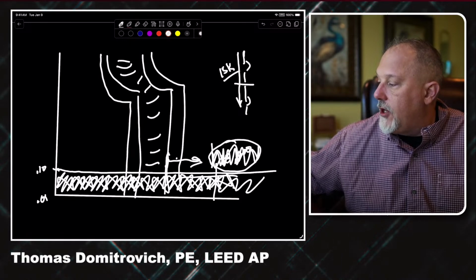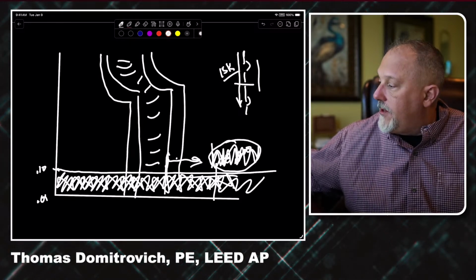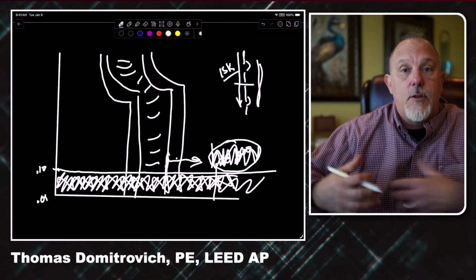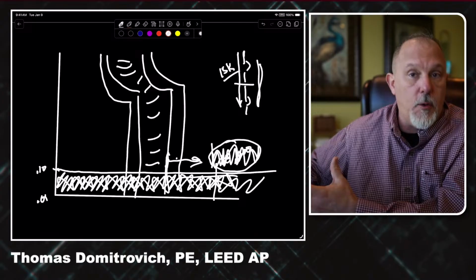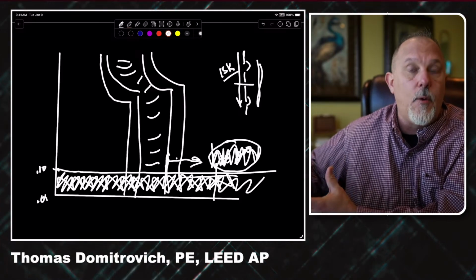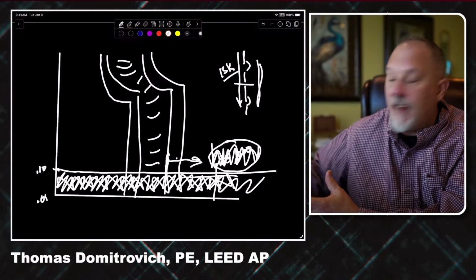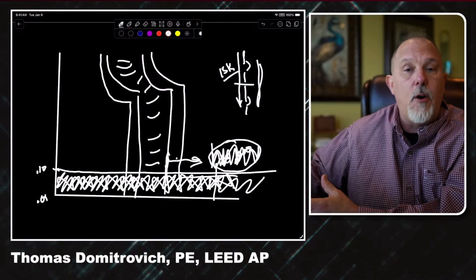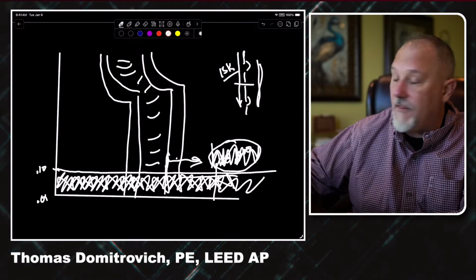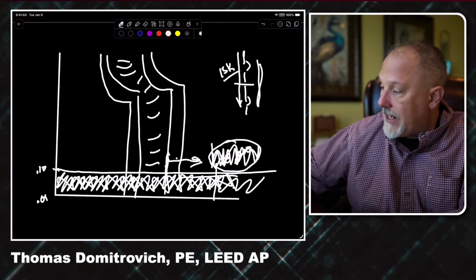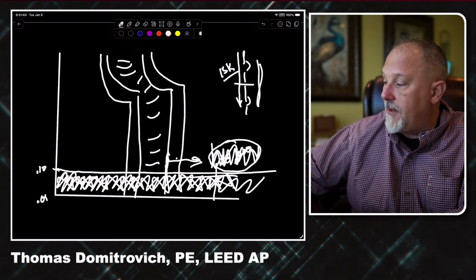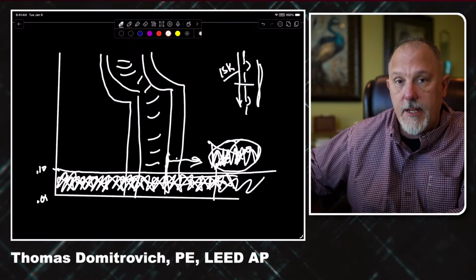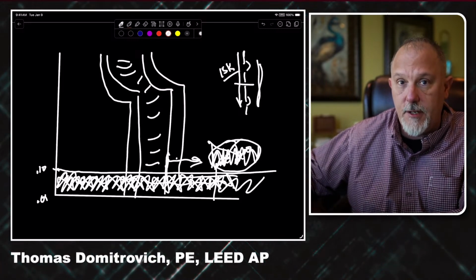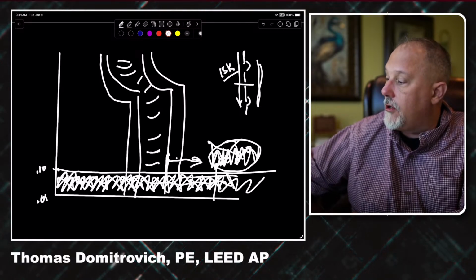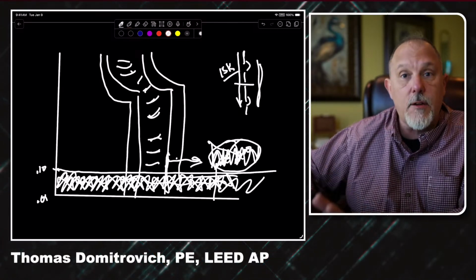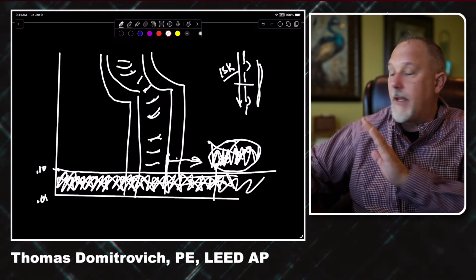If my current goes in that direction between those two devices, if I do a 0.1 second coordination, I can't tell you what will happen, because that evaluation did not occur. All the qualified person did was select two breakers and hide everything below 0.1 seconds. Did not calculate the fault current. Did not do a fault current evaluation against the time current characteristic curves and look for separation between the curves. That's all that's done. All right. That's all I'll say about that.